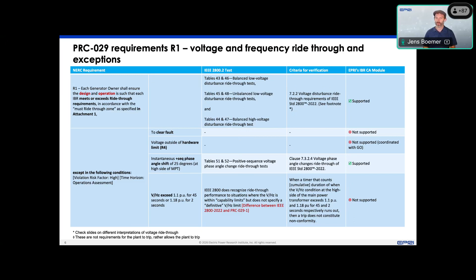Now, the exception of the instantaneous positive sequence phase angle shift is supported, and that is also related to specific tests in .2 for positive sequence voltage phase angle change ride-through. But then PRC 29 has a specific limit for the volt per hertz exception, whereas IEEE 2800 recognizes that potential capability limit, but does not specify a definite volt per hertz limit. So that is currently not supported in our tool, but as IEEE 2800 will be revised and that limit might be included in the next revision, more specifically similar to PRC 29, that certainly can be included using a timer.